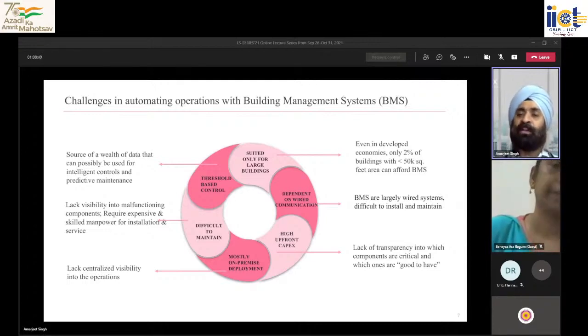Rather than putting a static temperature setting that runs the air conditioning at a fixed value like 25 degrees Celsius, perhaps run it based on data - if the occupancy of the building is lower, increase the set temperature, and if occupancy is higher, reduce the set temperature. So that data-driven operation, and data-driven fault detection and diagnosis, both of these things are missing in traditional BMS systems.